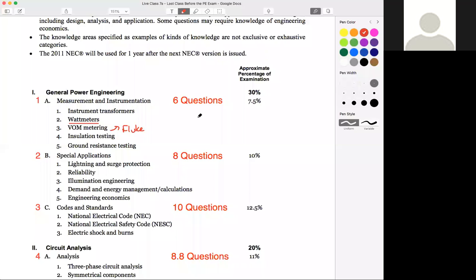Off the top of my head, who can tell me - if I want to measure current and I want to measure voltage, there's two distinctly different ways I have to hook up my meters. The hint is a watt meter, because a watt meter is composed of an amp meter and a voltmeter, and it demonstrates that clearly. If I want to measure current on a line, I have to break that line and put it in series with my meter - here's my amp meter, I have to put it in series. You cannot connect something across to measure amps - that's only for voltage. So if I want to measure voltage, that's perfectly okay. If I have two points on a system, I connect across them with my voltmeter, and that'll tell me the voltage drop from this point to this point. So those are two really good questions to know.